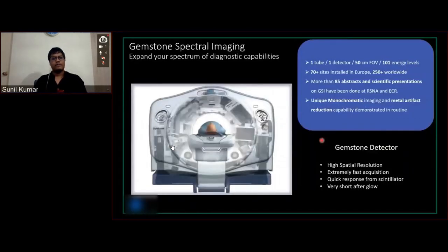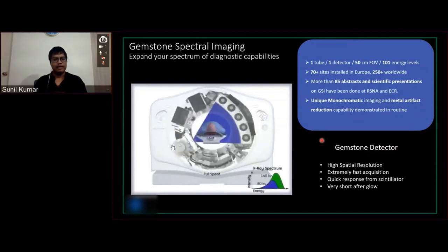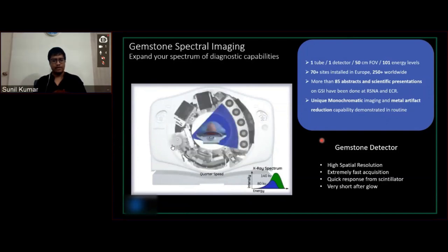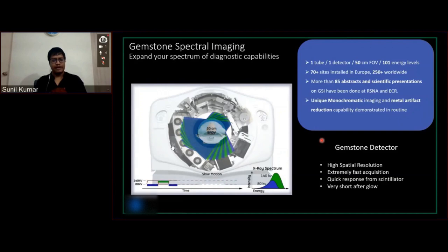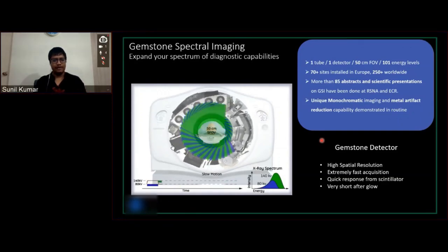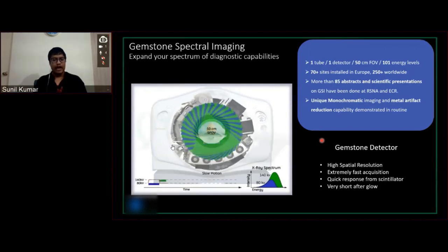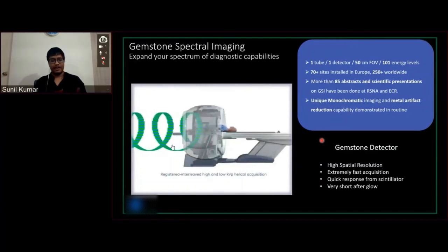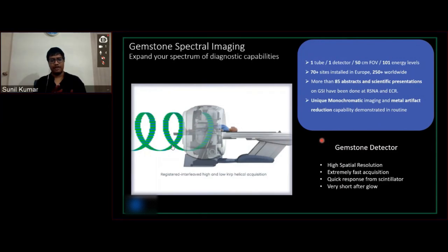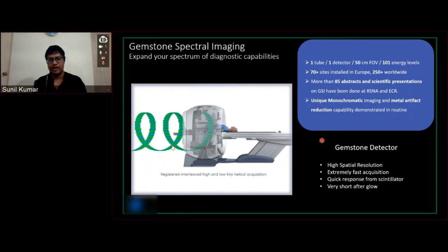The video running on screen shows how fast kV switching happens: the tube switches multiple times from 80 kV to 140 kV in one single rotation, with a delay of 0.25 milliseconds. We get interleaved high and low projections in a helical acquisition. Since we are so fast in acquiring, there's no extra dose for the patient and scan time remains the same — no increase in scan time, no increase in radiation dose. The spectral detector has high spatial resolution, one of the game changers of this technology in GE.